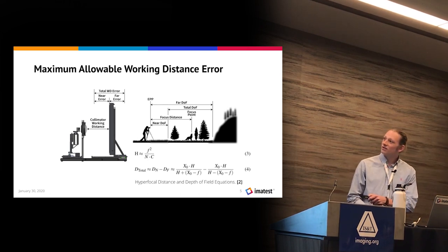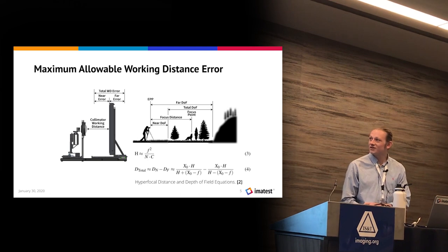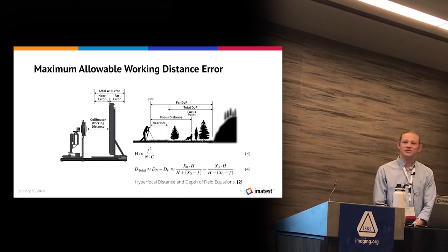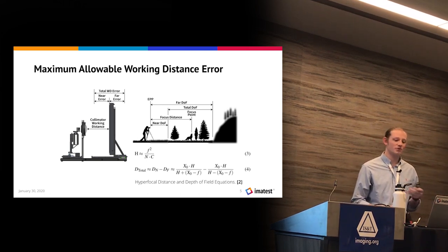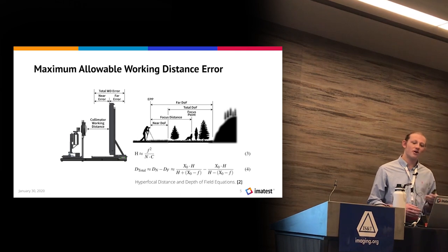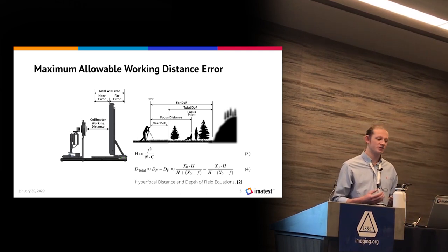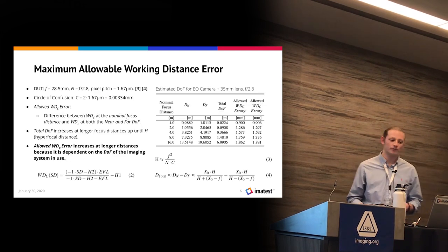Note that the image on the left is not to scale, as mechanical engineers would like to achieve much tighter tolerances than that diagram might have you believe. Basically, if the distances corresponding to the peak MTF in the real world and the collimator fixture measurements are both within the depth of field of the imaging system under test, the collimator fixture will pass validation.